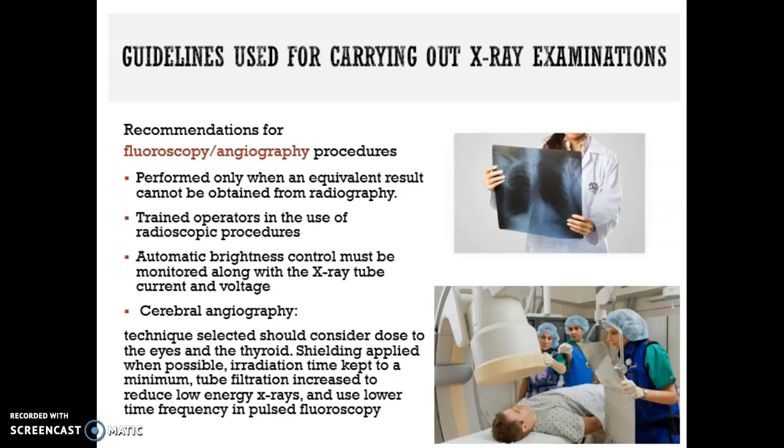Also, people working in these areas should be trained, and they need to know what they're doing because the exposures are higher than usual. Automatic brightness control, we have to be careful when it comes to this. It has to be monitored as it directly affects the tube current and the voltage, which obviously has a direct relationship to the patient's entrance skin dose.